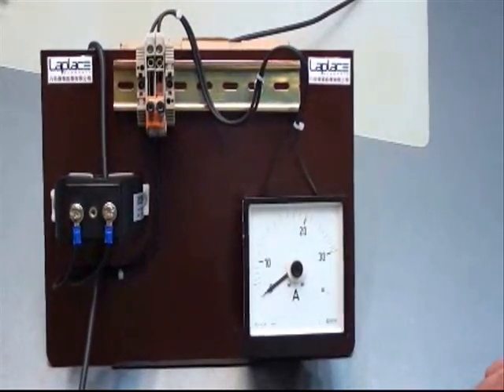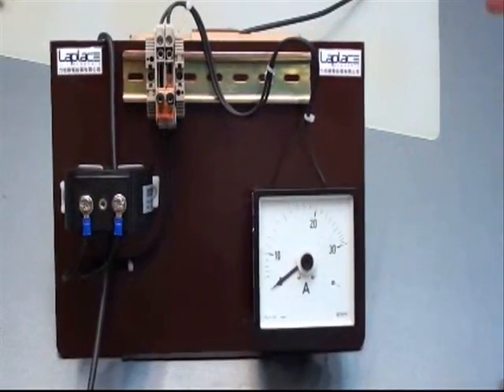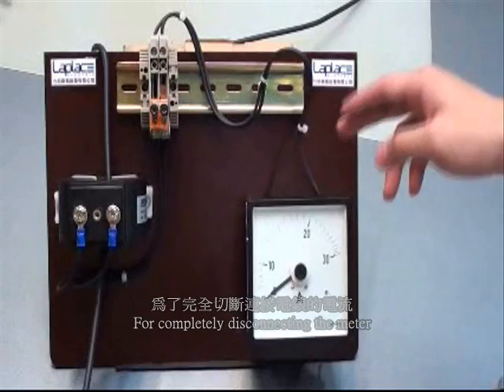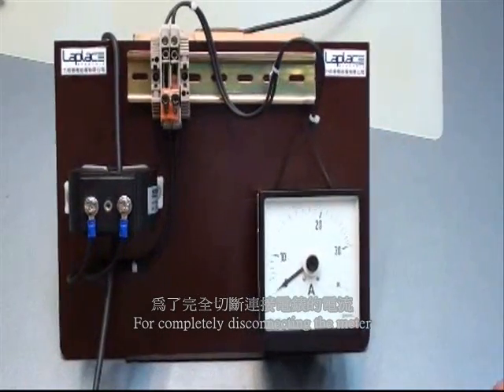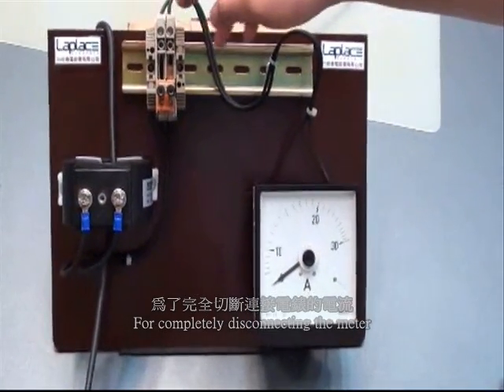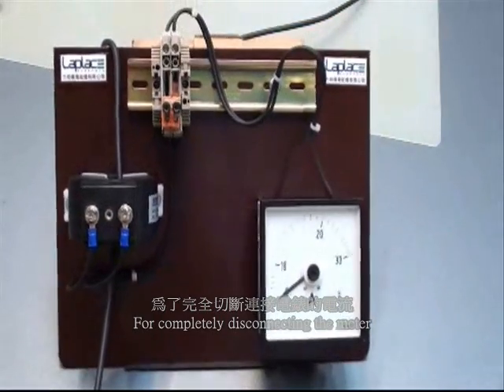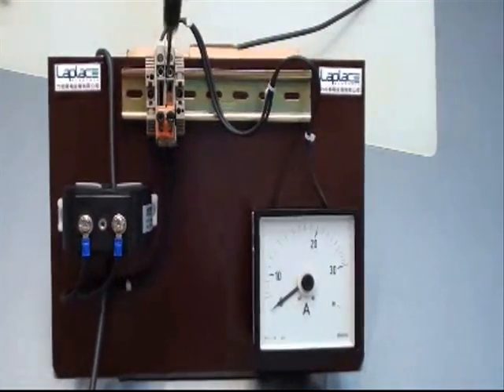Before we remove the meter, we will have completely disconnected the meter from circuit. The CT terminal provides the function to prevent open circuit. Remove this part.